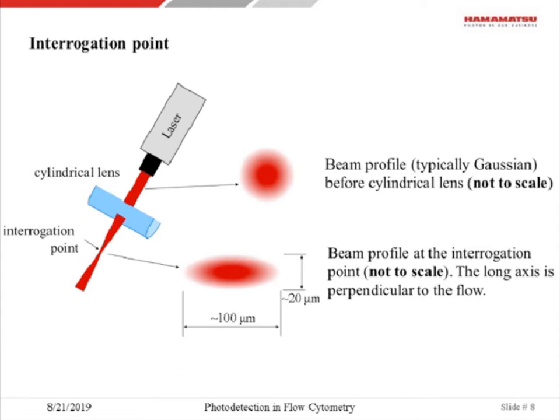Let's look more closely at the interrogation point. The interrogation point is defined by the light from a laser. In an ideal situation, when a cell passes the interrogation point, the amount of light falling on the cell would be independent of its location in the flow cell. For that to happen, we would like the light density in the interrogation point to be uniform. However, the output from a laser has a Gaussian profile, so one uses a cylindrical lens to stretch the beam profile, typically to sizes of about 100 by 20 micrometers, providing a flatter illumination profile.